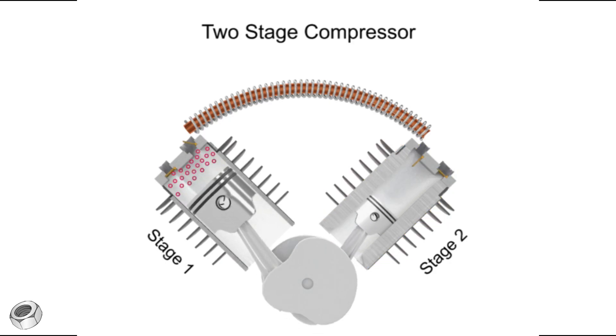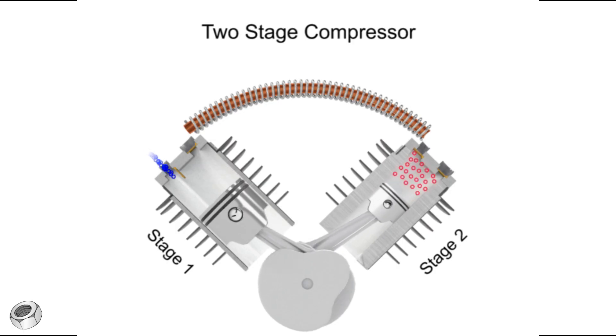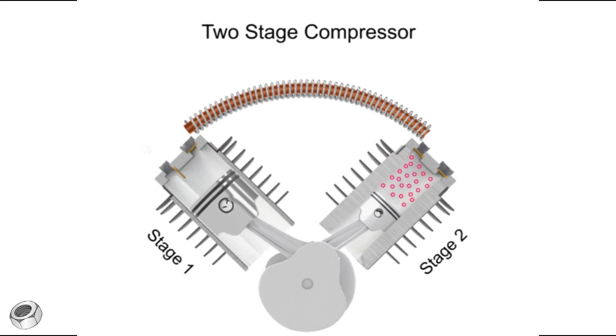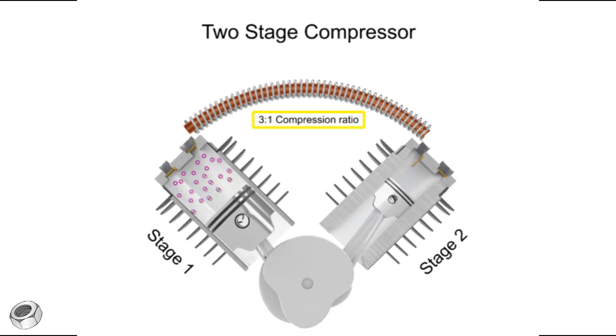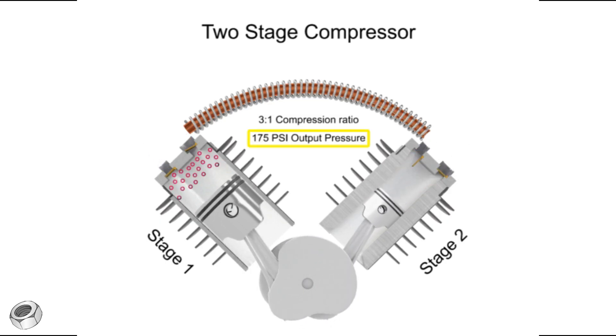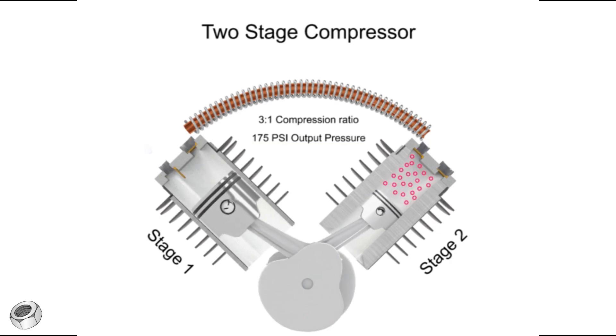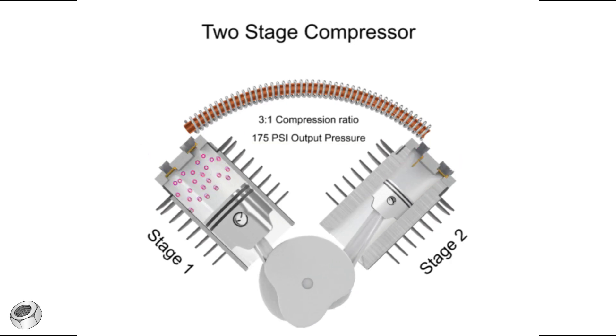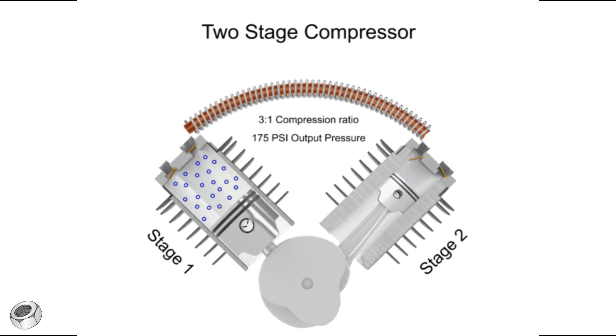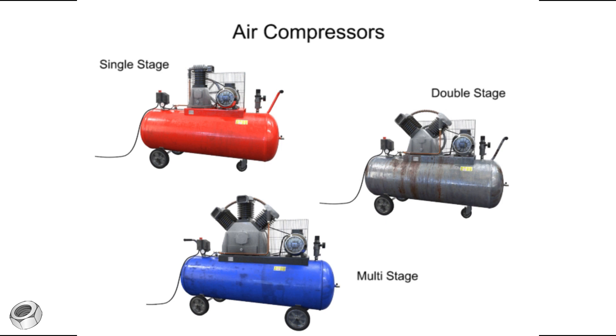The compressed air entering the second stage is sometimes called supercharged air. Two stage compressors have a compression range of 3 to 1 or even less per stage, but can operate up to 175 psi. They can also deliver more air at a higher pressure than single stage compressors of the same horsepower.